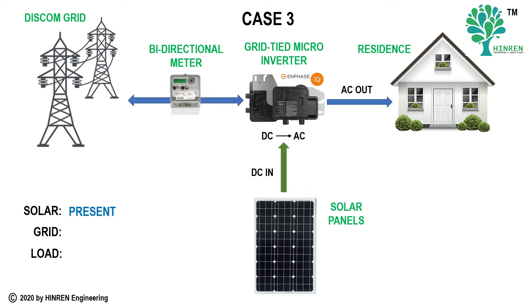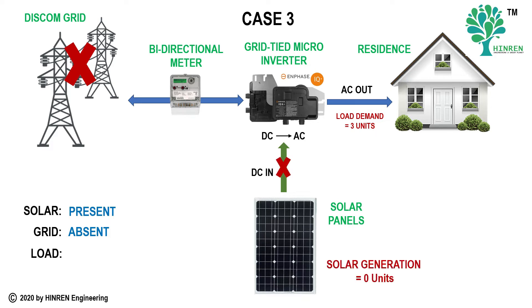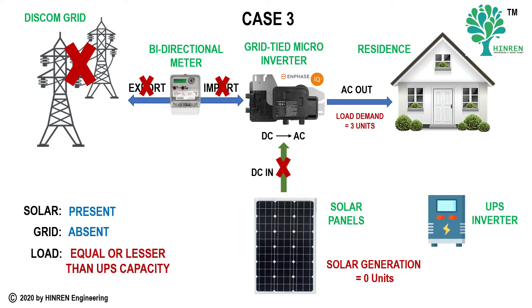In Case 3, the load demand is about 3 units and solar is available — however, the grid is absent due to either a power shutdown or maintenance. Since it is a grid-tie system, though solar panels are generating energy, that energy cannot be used and does not flow into the inverter. In an on-grid system, the presence of the DISCOM grid is mandatory for the system to work effectively. There is neither export nor import. If you have a UPS, you can run your loads through it.